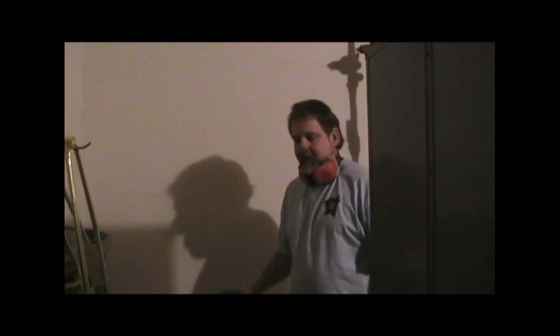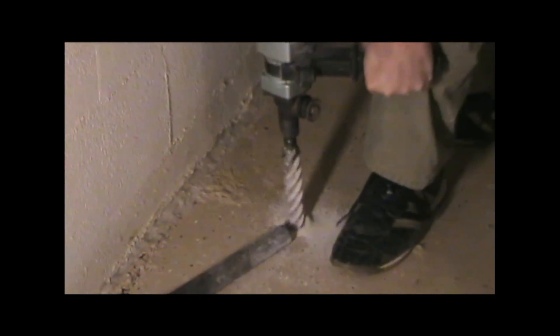What we're going to do now is shop vac diagnostics. We're going to make a small hole on the far end of the basement from our suction point, and a hole by the suction point large enough to get our vacuum hose in and take a pressure reading. When we turn the vacuum on over there, we hope to see the pressure change over here, which will let us know we're reaching all the way across and help with fan selection. I'm drilling an inch-and-a-half hole close to where the suction hole is going to be, and then we put our manometer down at the test hole on the other end.